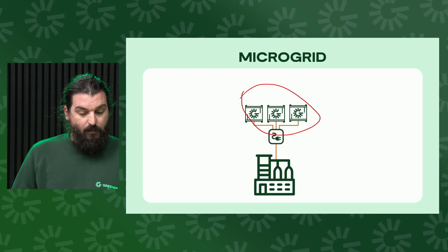I wanted to talk a little bit about the multi-battery solutions that we also offer. So we first create a microgrid, or a disconnected wire system. We have three batteries, which then have a total power of 750 kilowatts, or 1200 amps. So based on each container, in this case the greener container, 250 kilowatts per container, and we can also scale that up or down as needed. These will then be kind of Lego blocks doing individual parts, and then we can just add more or less in the right place in the network when necessary.